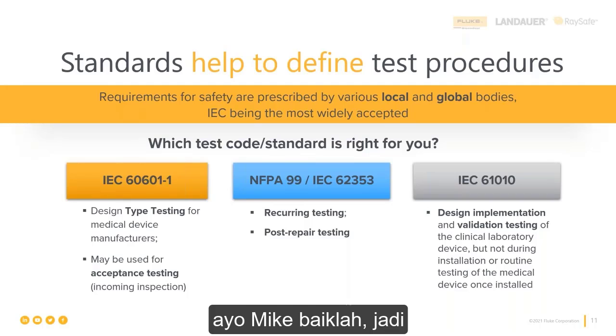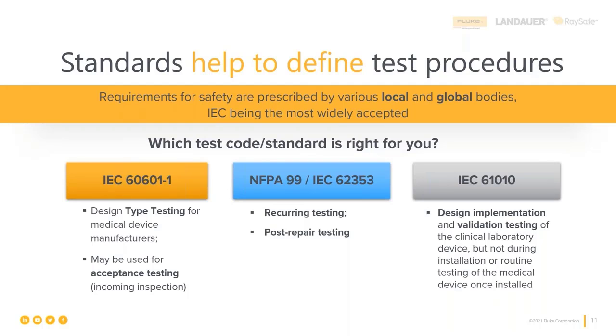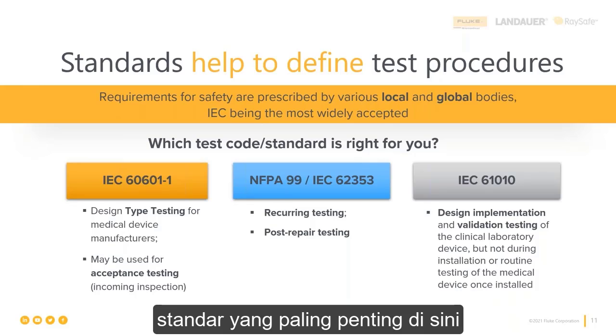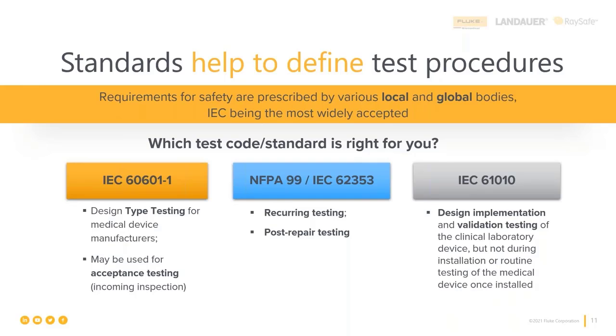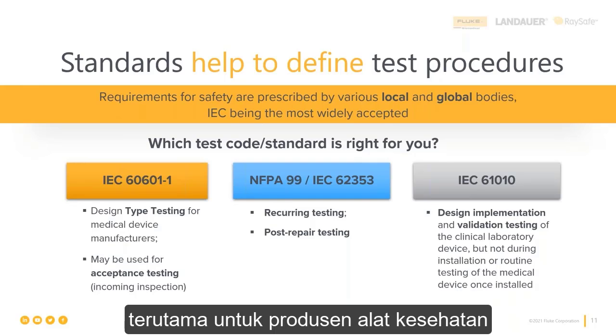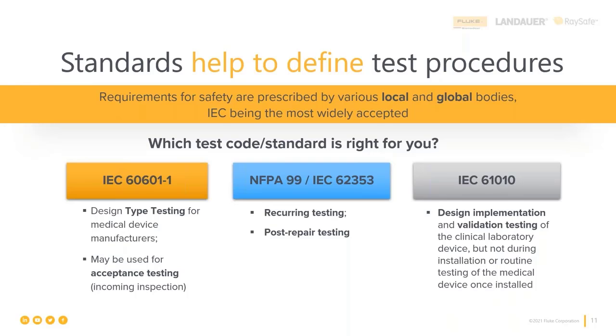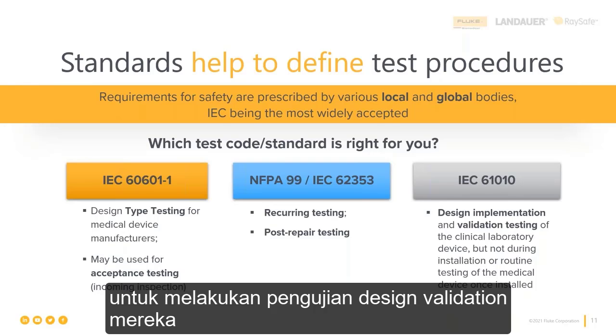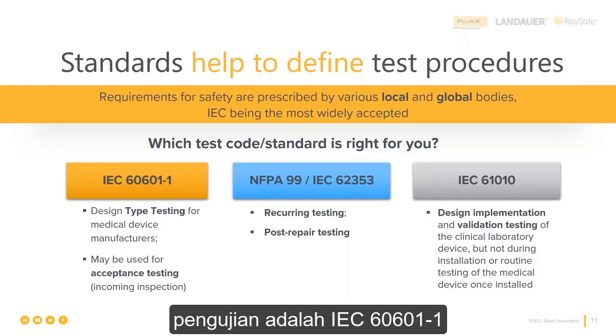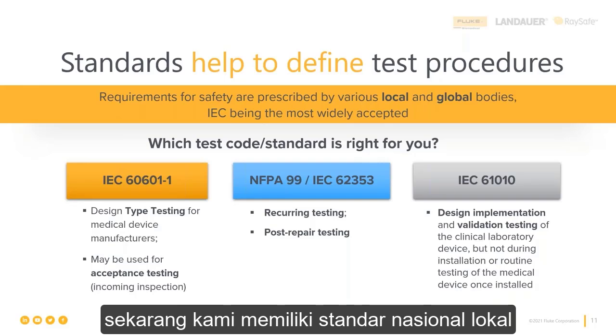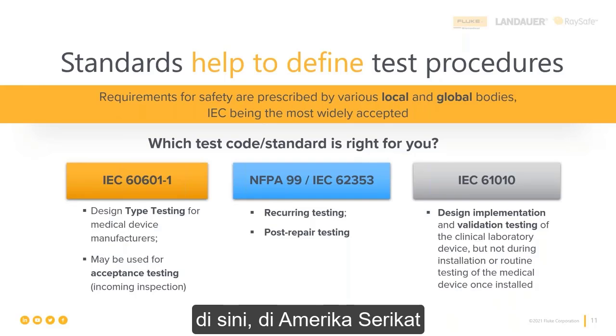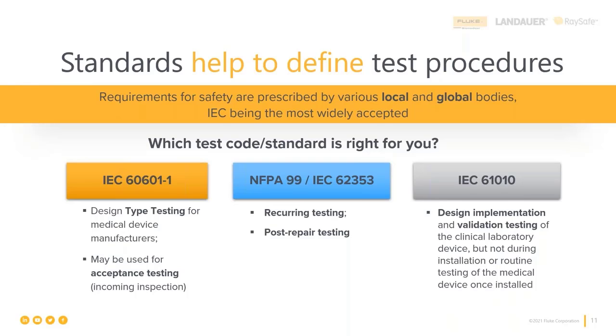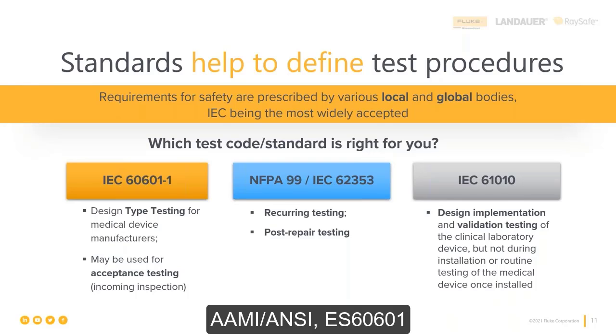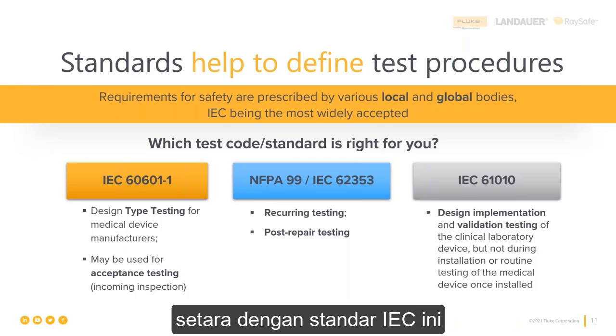All right, so in general, there are international standards. The big important one here, especially to medical device manufacturers for doing their design type testing, their design validation testing, is the IEC 60601-1. Now, we have a local national standard here in the United States, AAMI ANSI ES 601, which is harmonized and the direct equivalent of this IEC standard.